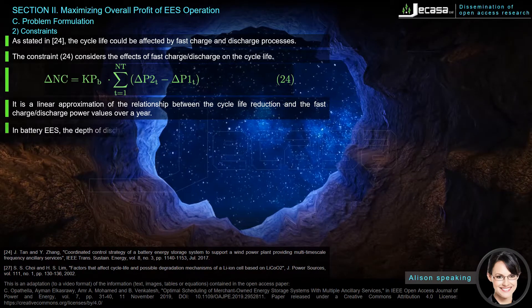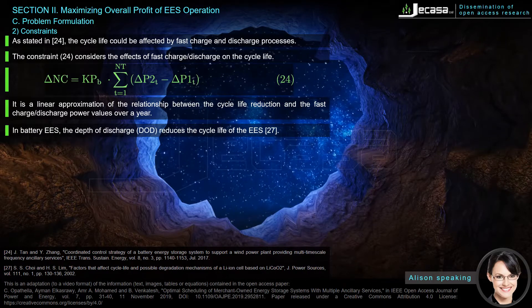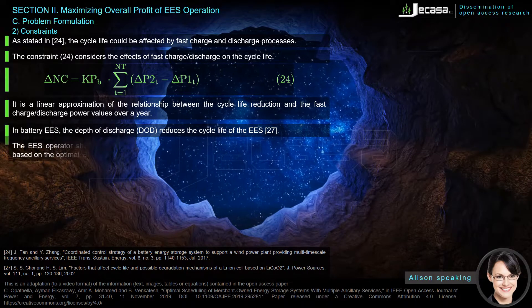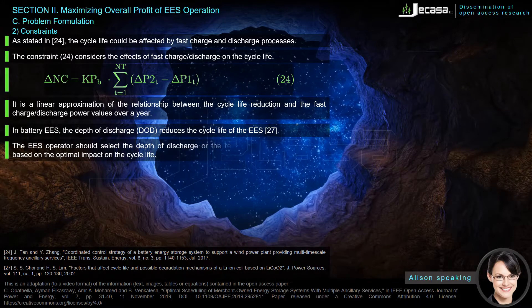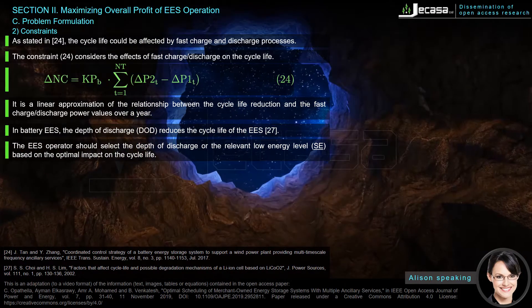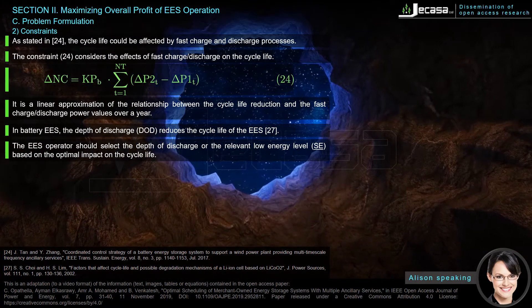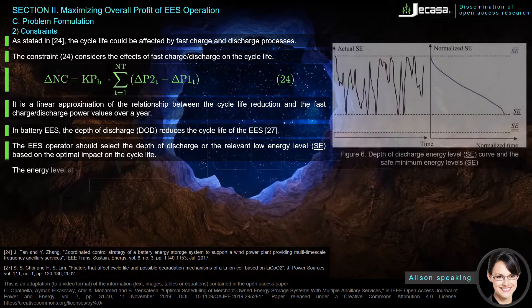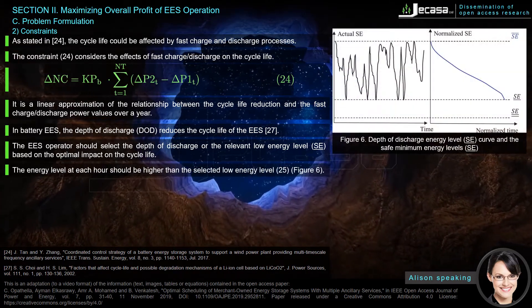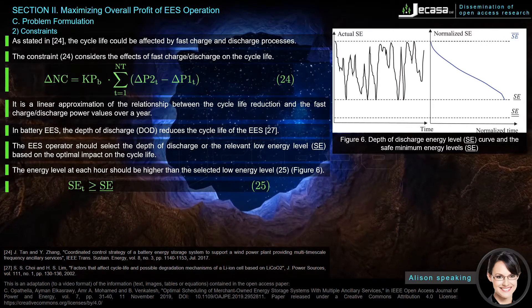In battery EES, the depth of discharge (DoD) reduces the cycle life of the EES. The EES operator should select the depth of discharge, or the relevant low energy level S_E, based on the optimal impact on the cycle life. The energy level at each hour should be higher than the selected low energy level, as given in equation 25 and Figure 6.